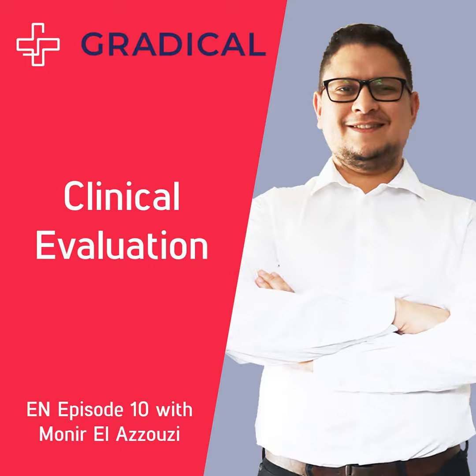A lot of companies don't want to go through clinical investigation because it's really a process that is long, costs money and everything. But as soon as you want to do a clinical investigation, you have to decide first where you want to do that. Do you want to do that, for example, in France or in the USA or in Brazil or in Switzerland or wherever? And then if you want to do it in a certain country, you have to contact this country, asking for the authorization to do this clinical investigation.